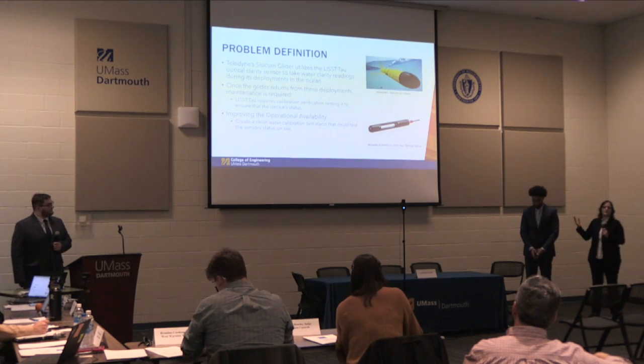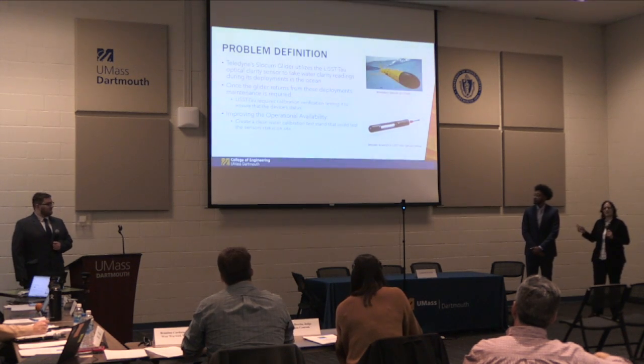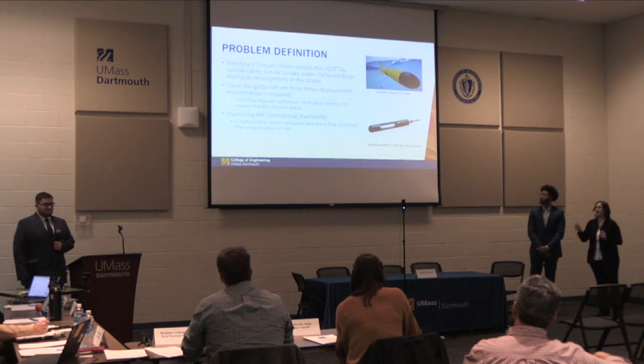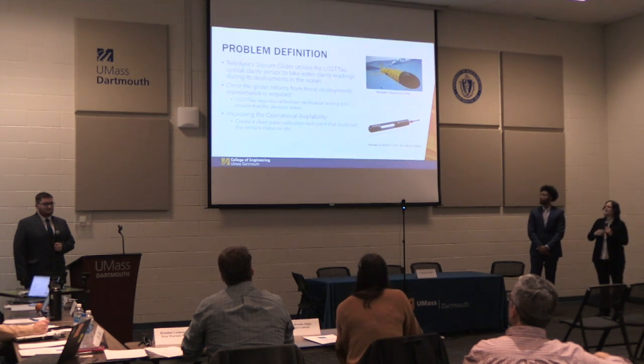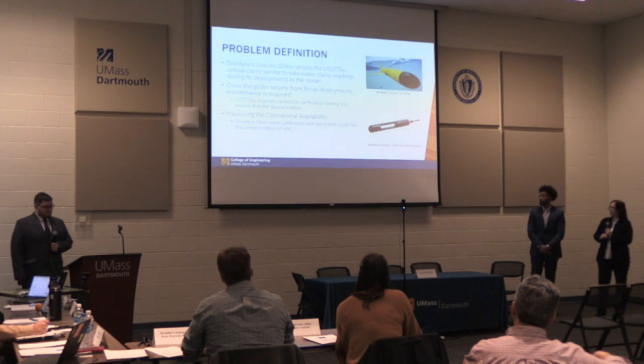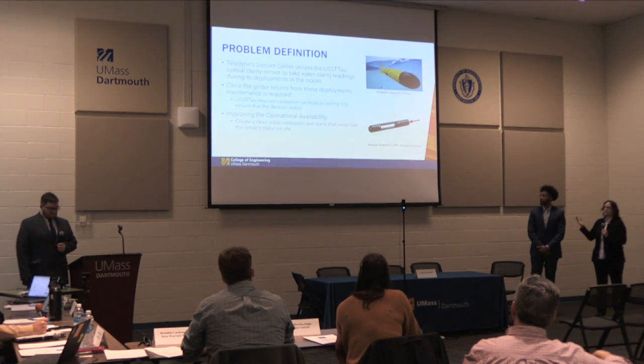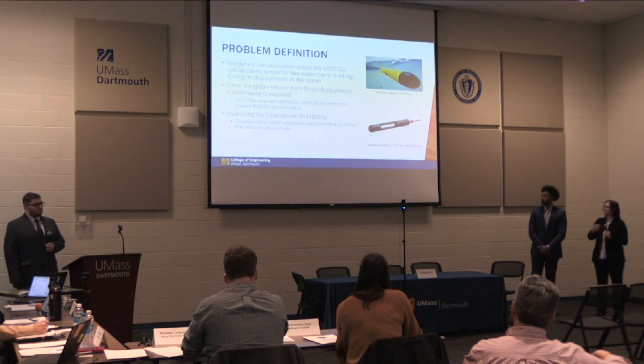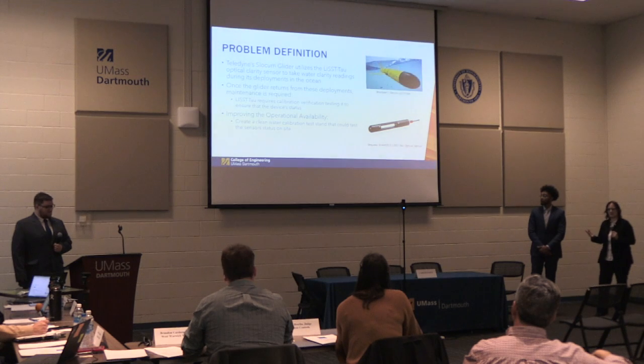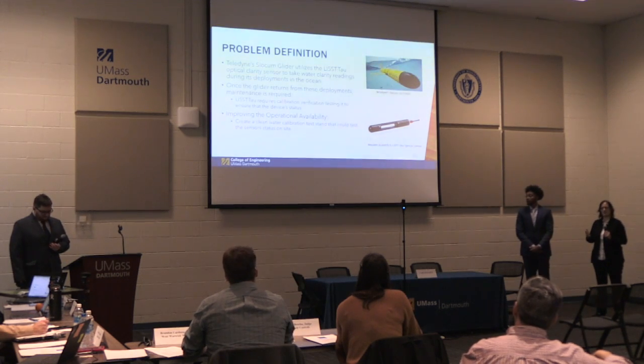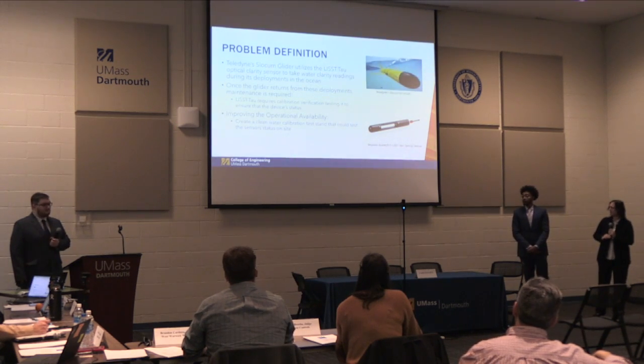So these LISST-Tau sensors are developed by Sequoia Scientific, and they are mounted to Teledyne Slocum Gliders. As these sensors are deployed into the ocean, they can become very easily fouled, especially due to how fine these sensor readings can be. So when these sensors are returned from deployment, they require calibration verification tests just to make sure that the baseline readings they're giving are still accurate.